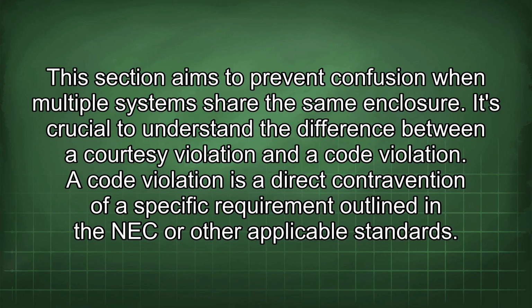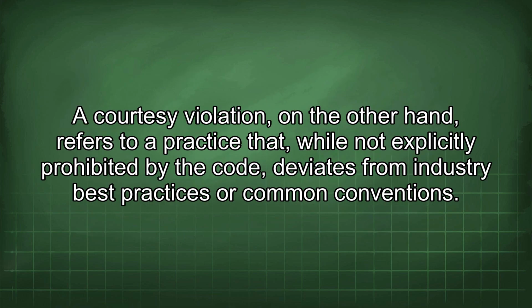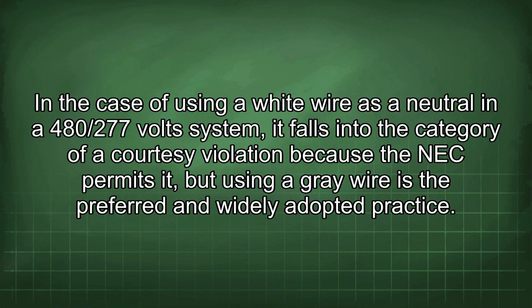It's crucial to understand the difference between a courtesy violation and a code violation. A code violation is a direct contravention of a specific requirement outlined in the NEC or other applicable standards. A courtesy violation, on the other hand, refers to a practice that, while not explicitly prohibited by the code, deviates from industry best practices or common conventions. In the case of using a white wire as a neutral in a 480/277 volt system, it falls into the category of a courtesy violation because the NEC permits it, but using a grey wire is the preferred and widely adopted practice.